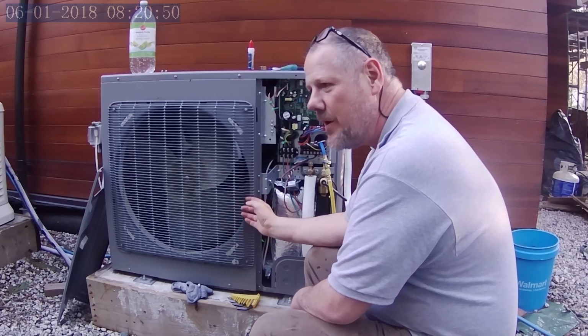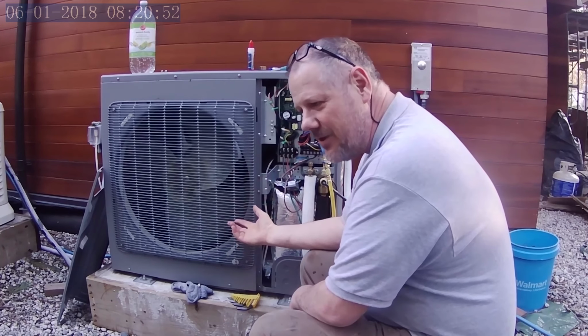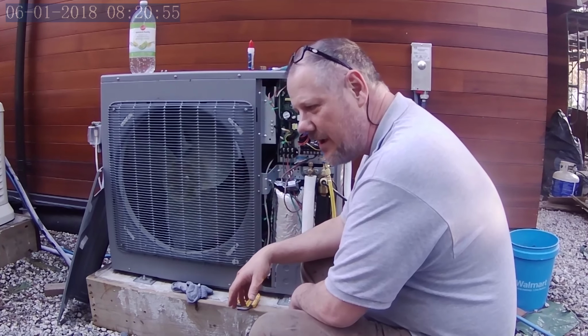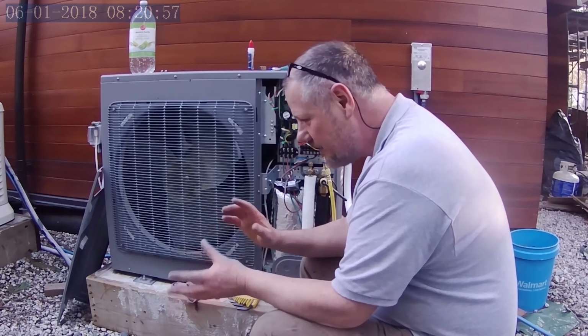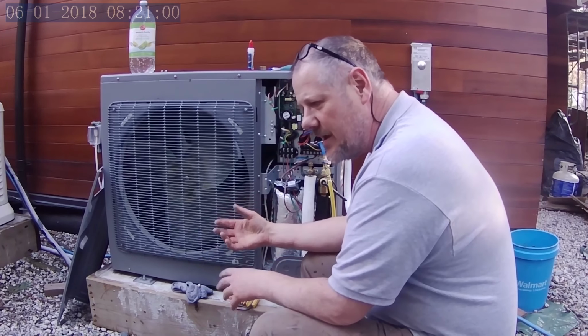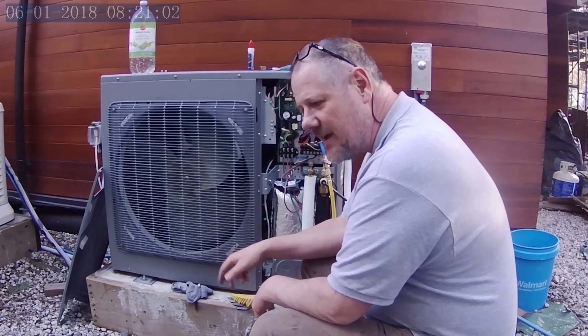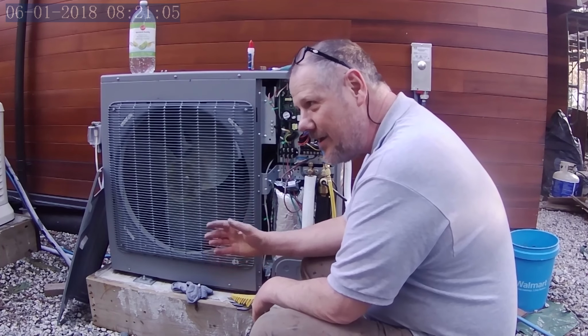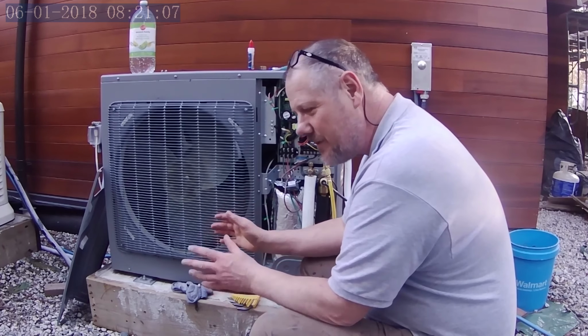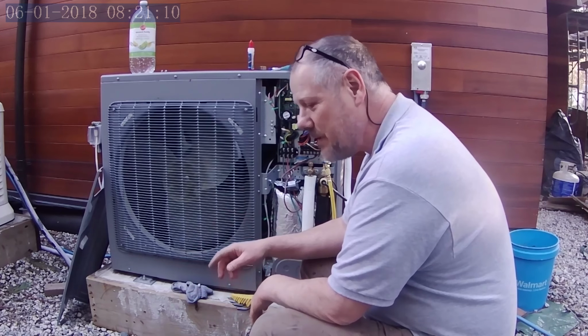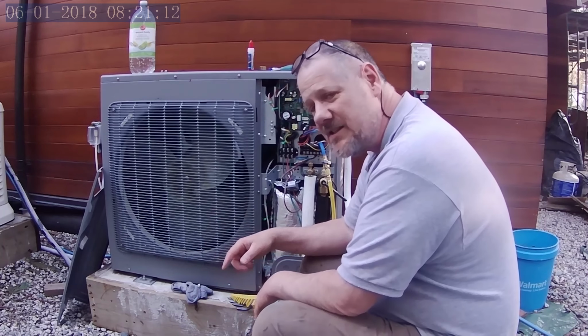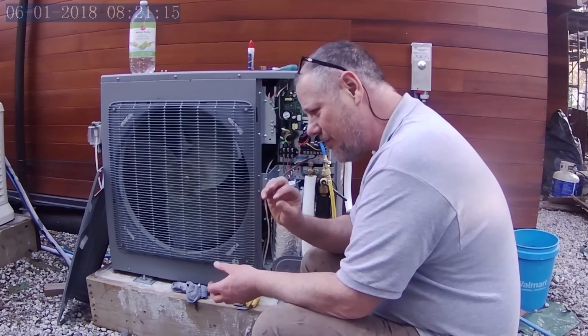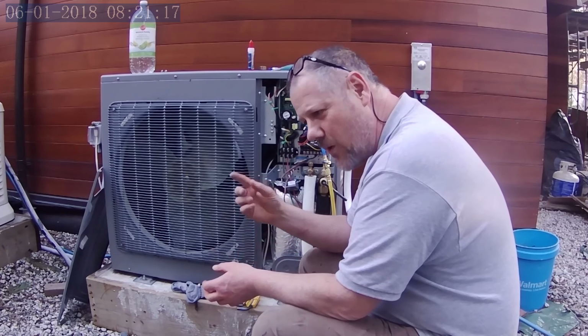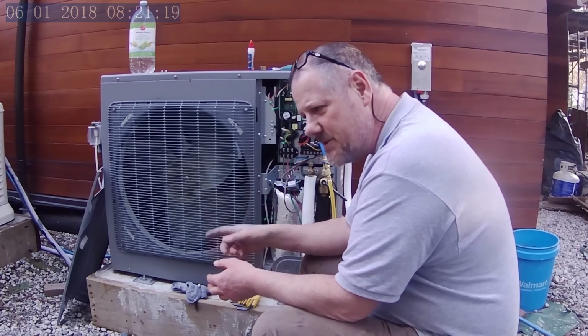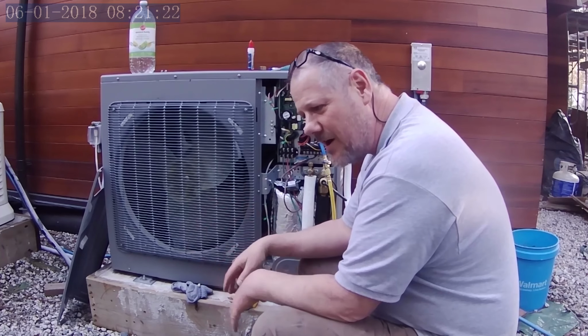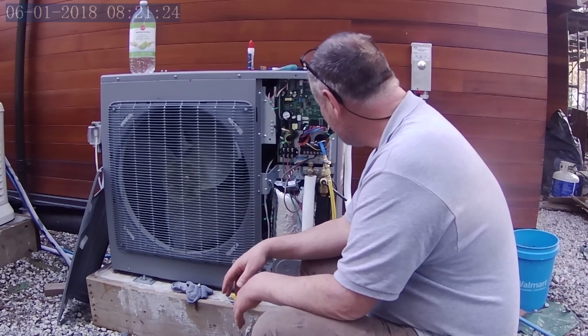Remember that this is meant to go with a GREE indoor air handler, and we are mixing it up in a prototype situation with the ThermAtlantic DX2W EX1 indoor expansion exchange module. So it's basically, if I understand it right, a spiral heat exchanger. It has the refrigerant going in one of the pipes and the water going the opposite direction in the other intimate contact pipes to transfer the heat.